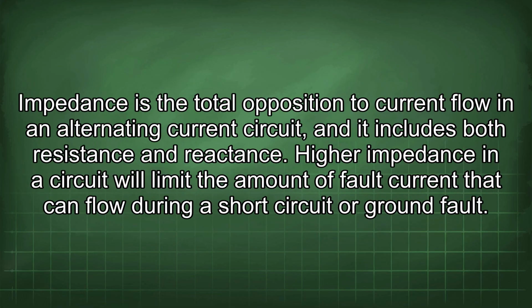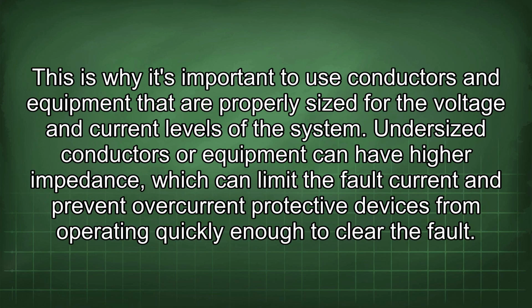Impedance is the total opposition to current flow in an alternating current circuit, and it includes both resistance and reactance. Higher impedance in a circuit will limit the amount of fault current that can flow during a short circuit or ground fault. This is why it's important to use conductors and equipment that are properly sized for the voltage and current levels of the system. Undersized conductors or equipment can have higher impedance, which can limit the fault currents and prevent overcurrent protective devices from operating quickly enough to clear the fault.